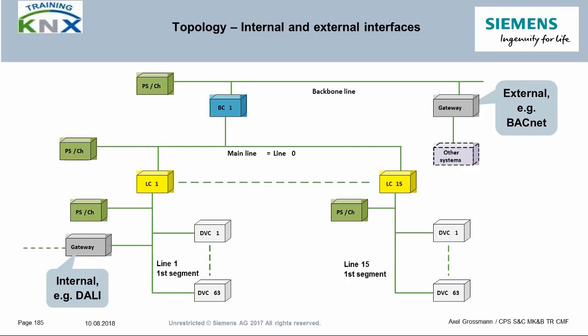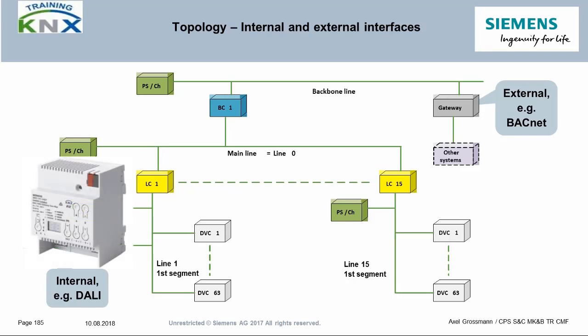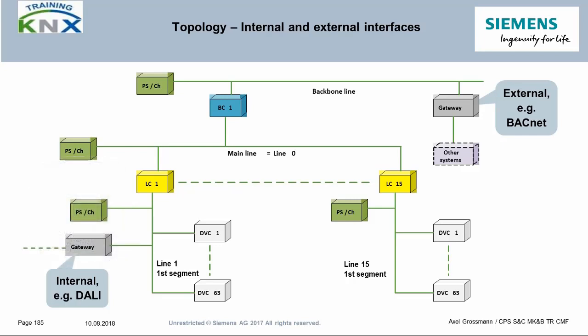As for internal interfaces, the KNX bus is a frequent host for the lighting bus called DALI. Such gateways must be in the sublines, but the possible telegram traffic load must also be observed closely, since a DALI line can have up to 64 dimming channels plus scene control plus 16 sensors.